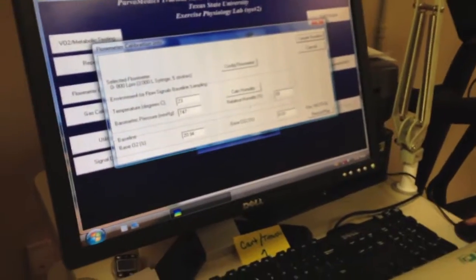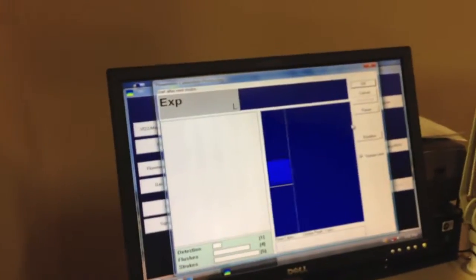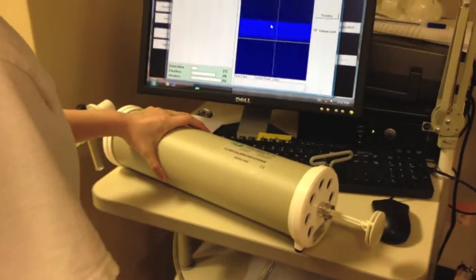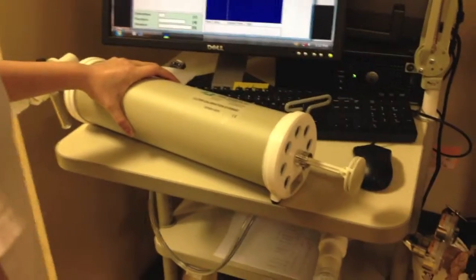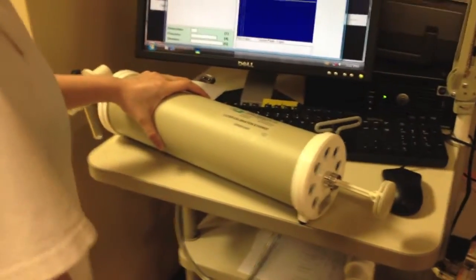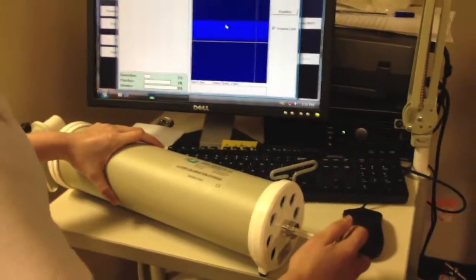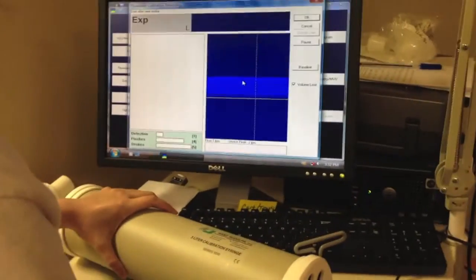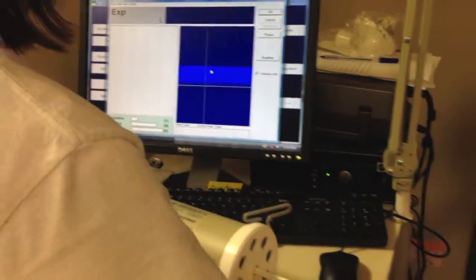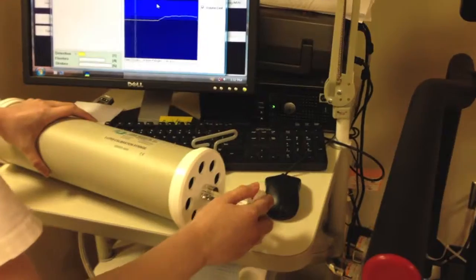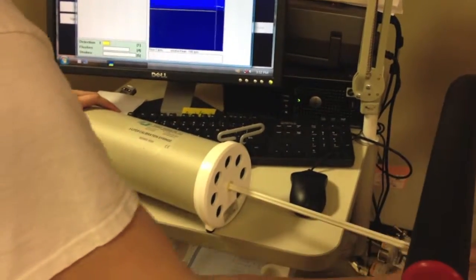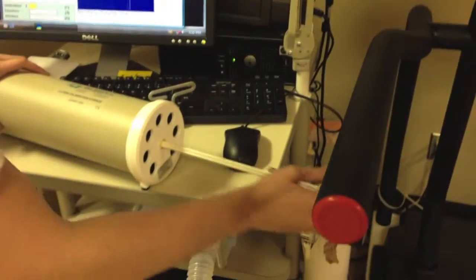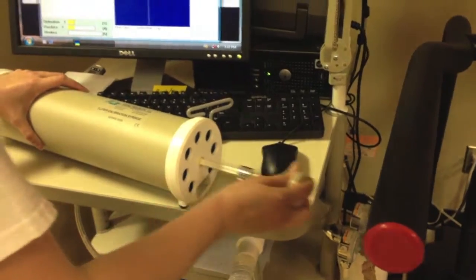A prompt screen will come up. You will press sample baseline. You'll start with the syringe plunger pressed all the way in, as shown. This step calls for 5 strokes, the first being a detection stroke and the other 4 being flush strokes to ensure accuracy in the calibration. You will need to be sure to pull and push the syringe plunger all the way in and all the way out.